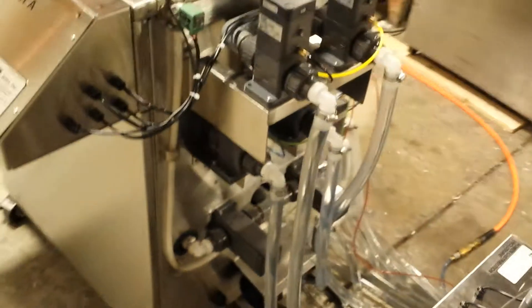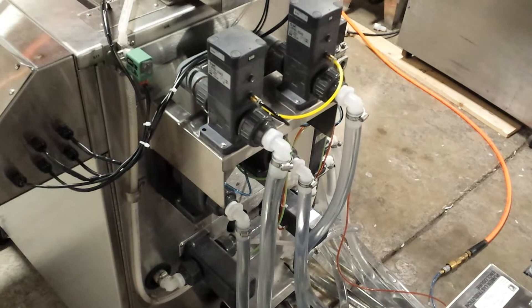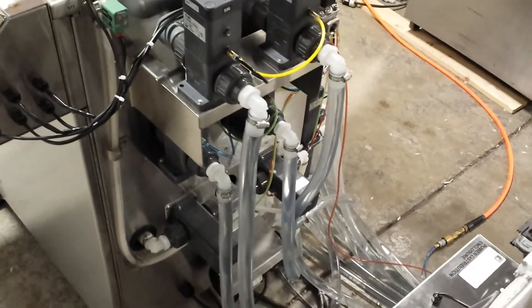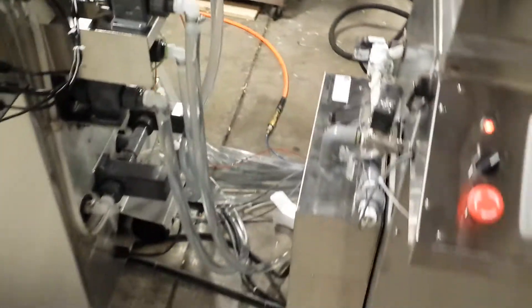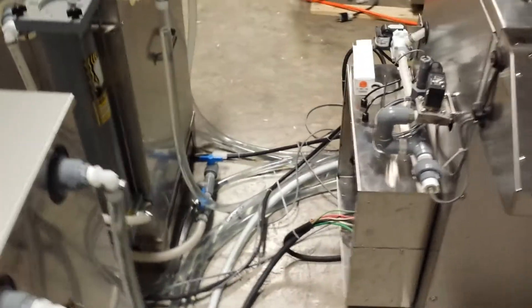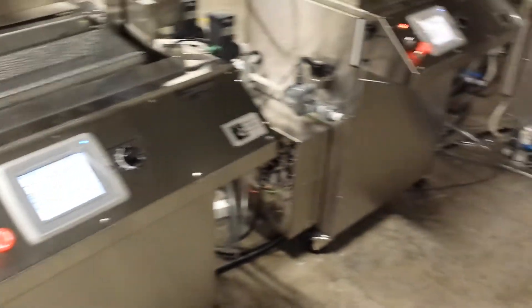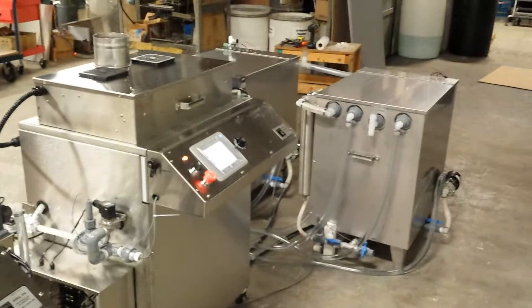The system uses mag drive pumps, including chemically compatible ones, and the valves are CPVC and air actuated. The hoses used to connect the machine are PVC hose with custom lengths, so the modular system can be configured in whatever way fits the building or room application.